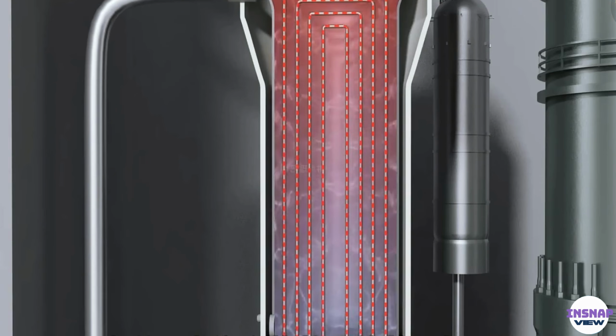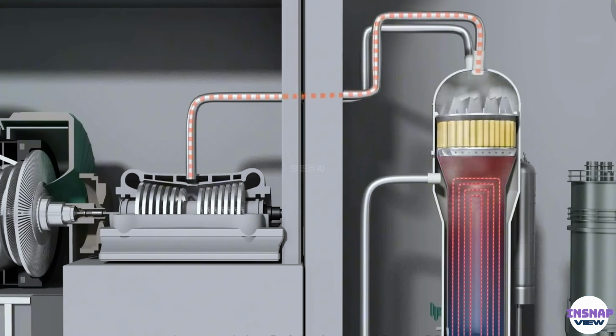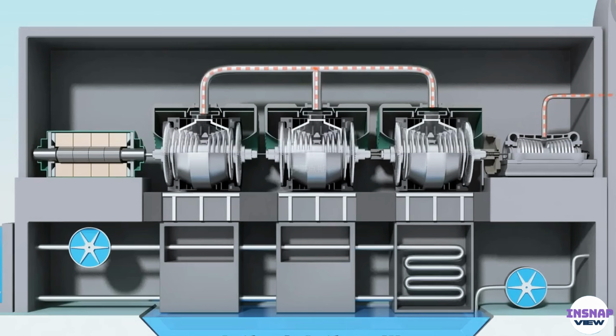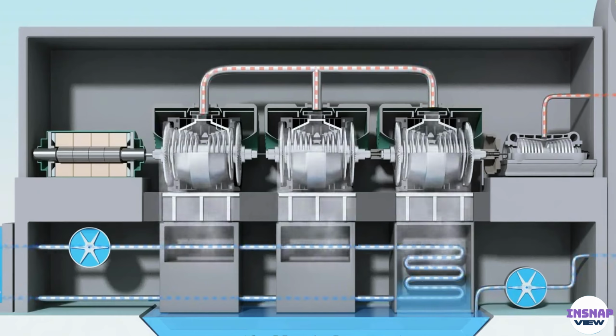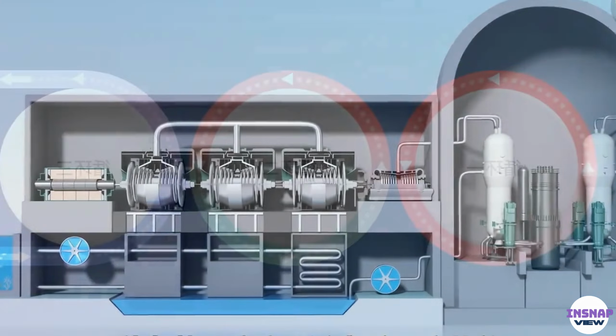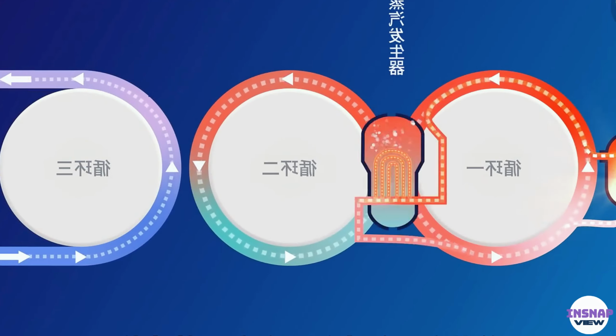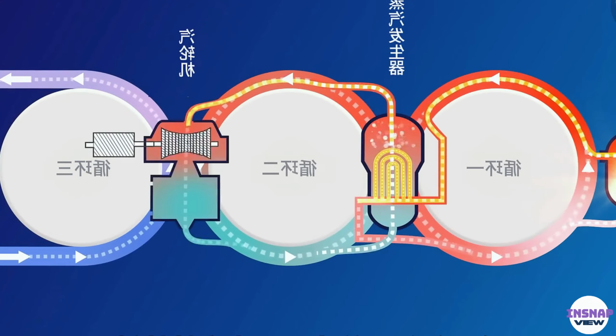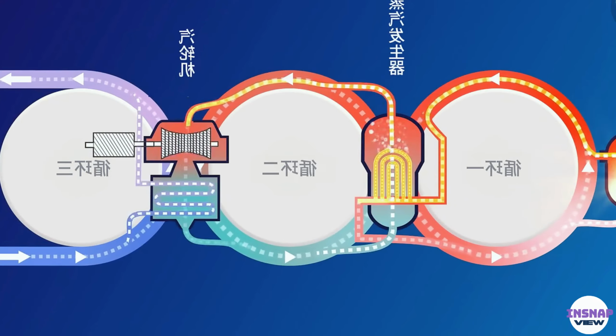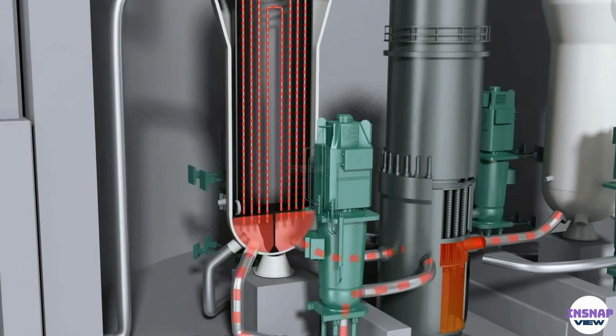The hot water heats the water in the steam generator through a high-temperature water pipe, generating steam. After the steam pushes the turbine to turn, it drives the generator to generate electricity. Steam is cooled into liquid water by seawater and returned to the steam generator. There are 3 water cycles involved in heat exchange. None of these 3 sets of circulating water come into direct contact.